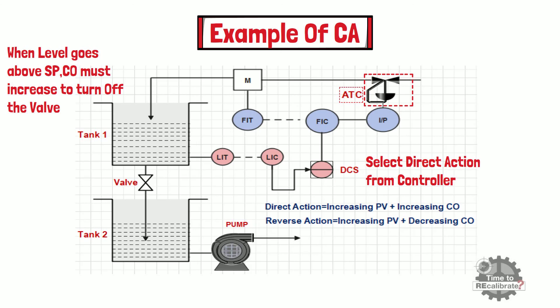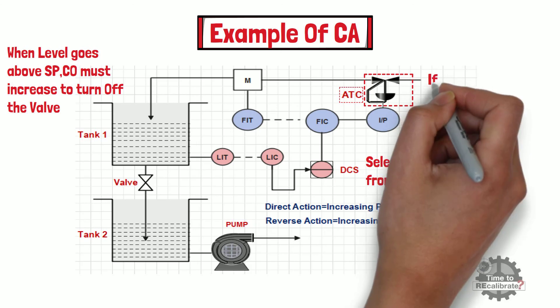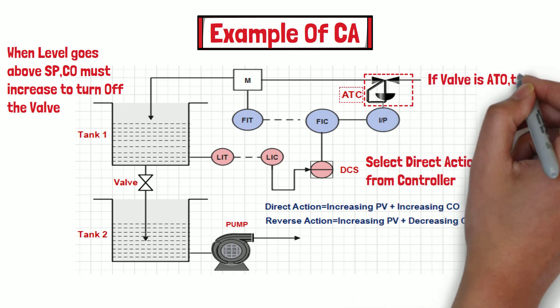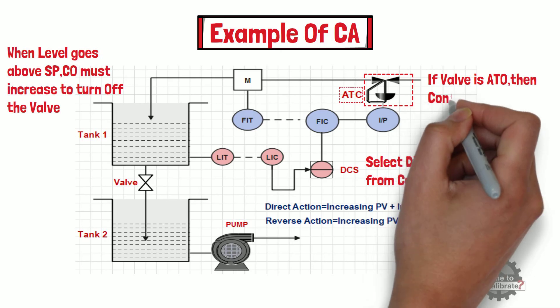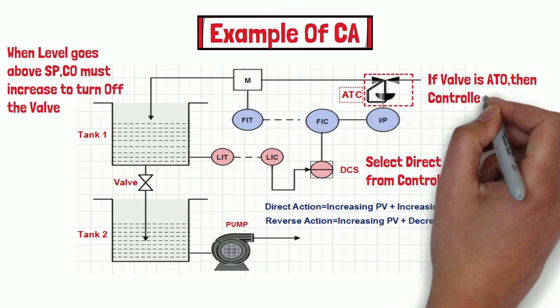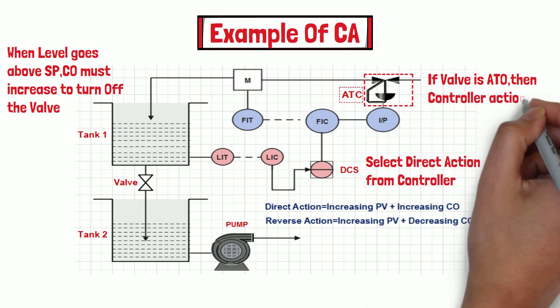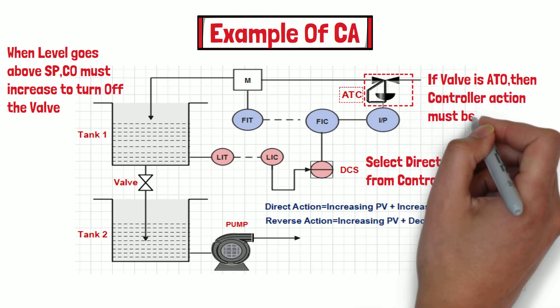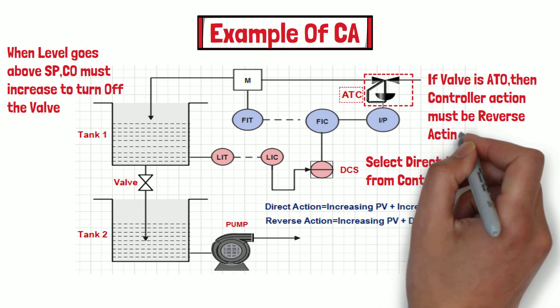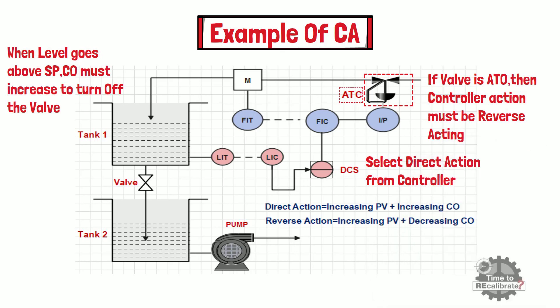Now let's assume that we have used an air-to-open control valve in this example instead of air-to-close. In this case, when the level of tank 1 goes above set point, to correct the error the controller output must decrease to turn off the flow in tank 1. Hence, reverse action needs to be selected from the controller.